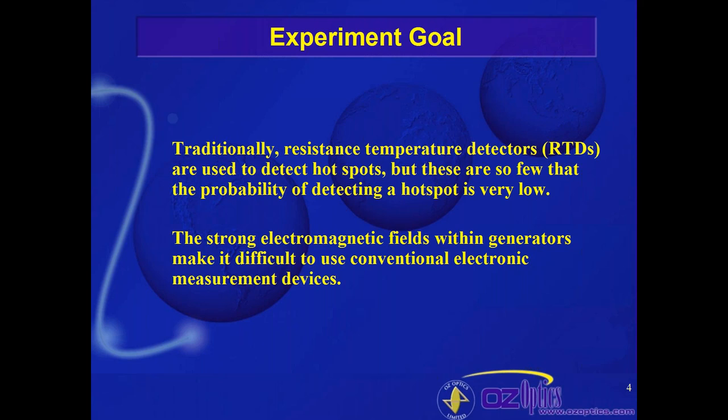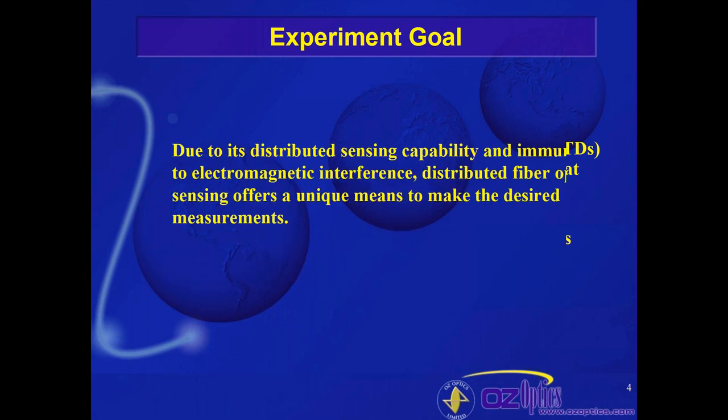The beauty of having distributed fiber optic sensing is that it gives you a distributed temperature profile, so you can see what's happening basically anywhere along the length of the fiber. Another advantage of using fiber optic sensing is that you avoid the problems associated with strong electromagnetic fields. These electromagnetic fields exist within generators and make it difficult to use conventional RTDs or other electronic devices because they introduce a lot of noise and make accurate, repeatable measurements hard. When you use fiber optic sensing, you get around that problem because it is immune to electromagnetic fields. This means fiber optic sensing is nearly an ideal method for making temperature measurements where you want a complete picture of what's going on inside the generator.